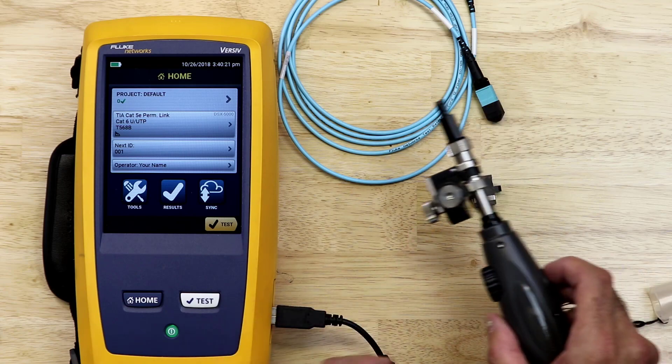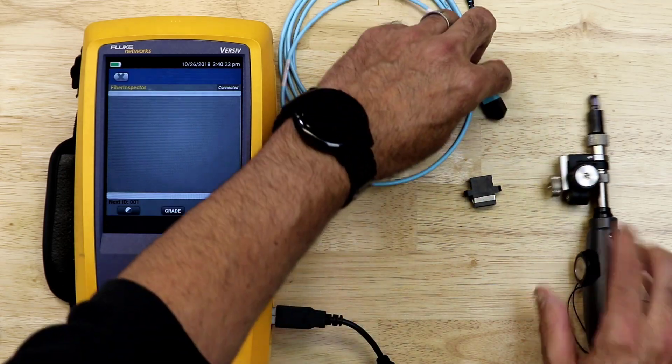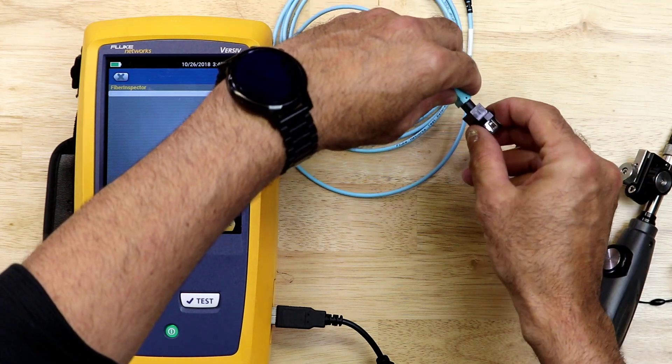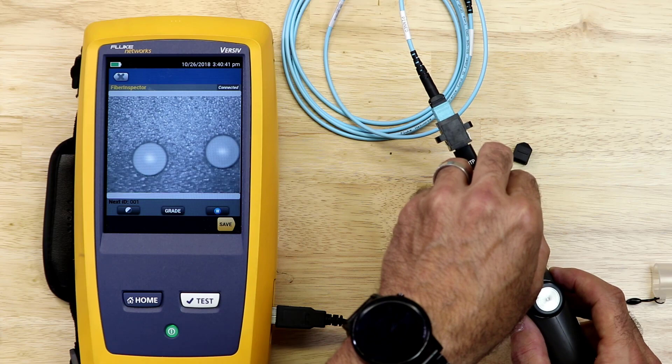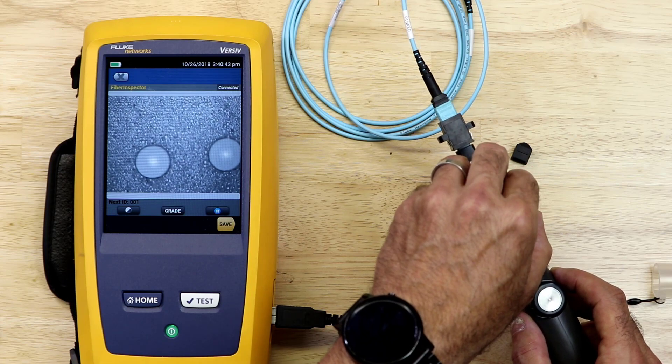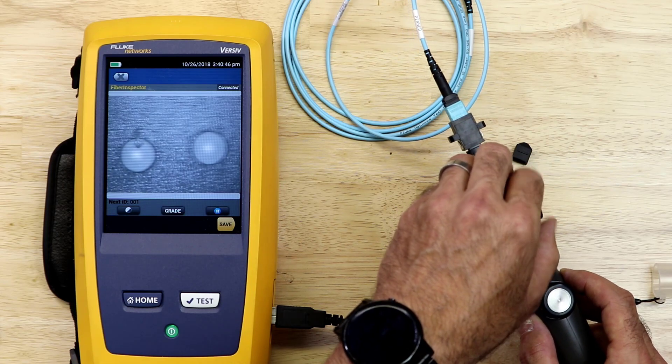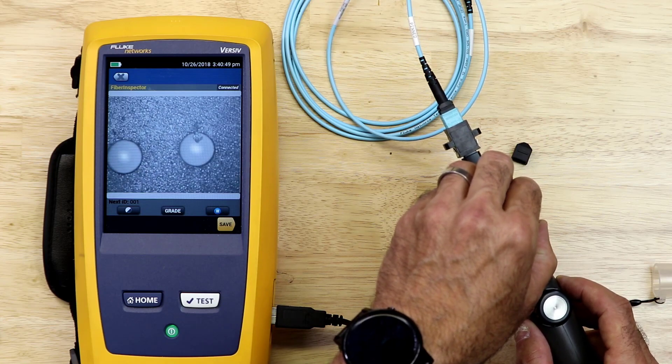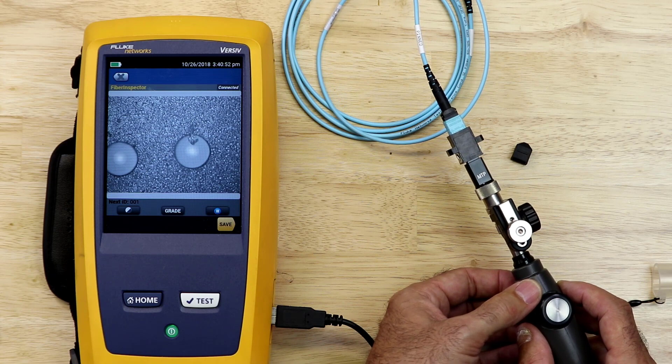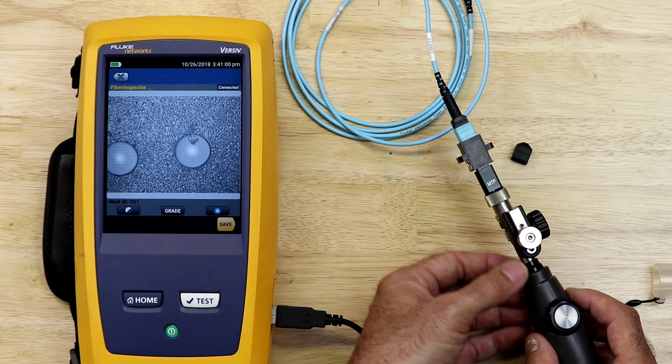On the Versiv mainframe, I will select the fiber inspection tool. Next, I will connect a bulkhead adapter to the MPO connector I'm going to test. I've found it's much easier to connect the bulkhead adapter first and then connect it to the camera. Here we can see the end face of the MPO connector on the screen of the Versiv mainframe. By rotating the knobs on the MPO inspection adapter, I can center the end faces in the screen and move across the end of the connector. It is important that we inspect all 12 of the end faces before connecting the fiber to our test equipment or other fibers. Here I can see that I've got an end face with some dirt on it.